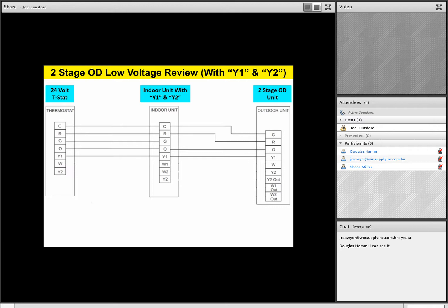C is 24 volt common, and that's going to go all the way from the thermostat to the indoor unit to the outdoor unit. That'll just be a straight run all the way through. This is pretty common and straightforward on low voltage wiring. Your R terminal is your 24 volt hot, and it would go between R to R on the indoor unit to R outside, which is going to be your 24 volt hot, powering all those components up on the 24 volt system. Your G terminal from the thermostat will go directly to the indoor unit to the G terminal, and that will be your fan terminal. Basically, when the thermostat calls for fan operation, it'll energize the G terminal, and the indoor unit will have that G signal for fan operation.